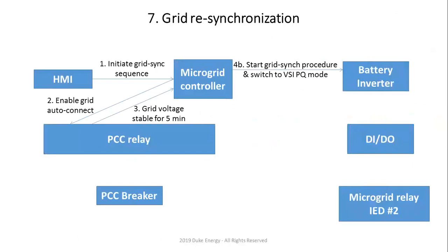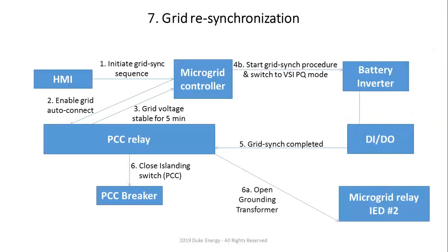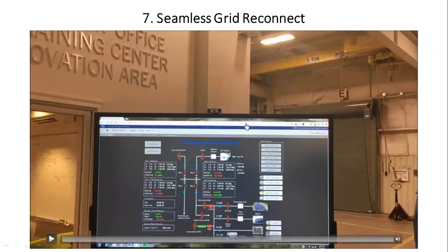So that's done through that scheme where we tell the battery inverter that we need to go back to the grid. So the battery is going to change from VSI ISO to the VSI VF mode. And when the battery syncs up, it's going to tell the PCC relay that the grid sync has completed. The PCC relay is going to check its own 25 settings. If everything is fine, it's going to close the islanding switch. And we're going to tell another relay to open the grounding transformer, right? And then when that happens, we're going to tell that PCC has closed, that we didn't have breaker failure or anything like that. So that's a simplified version of what happens, right? And the battery inverter is going to stop the sync procedure because it's going to go back to the VSI PQ mode, right?